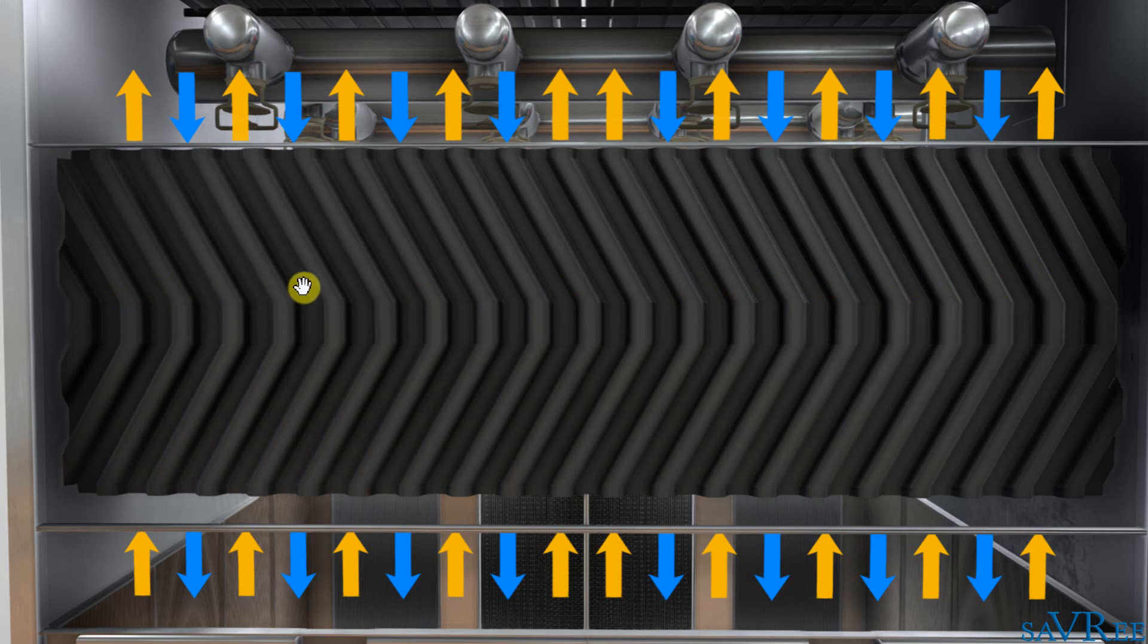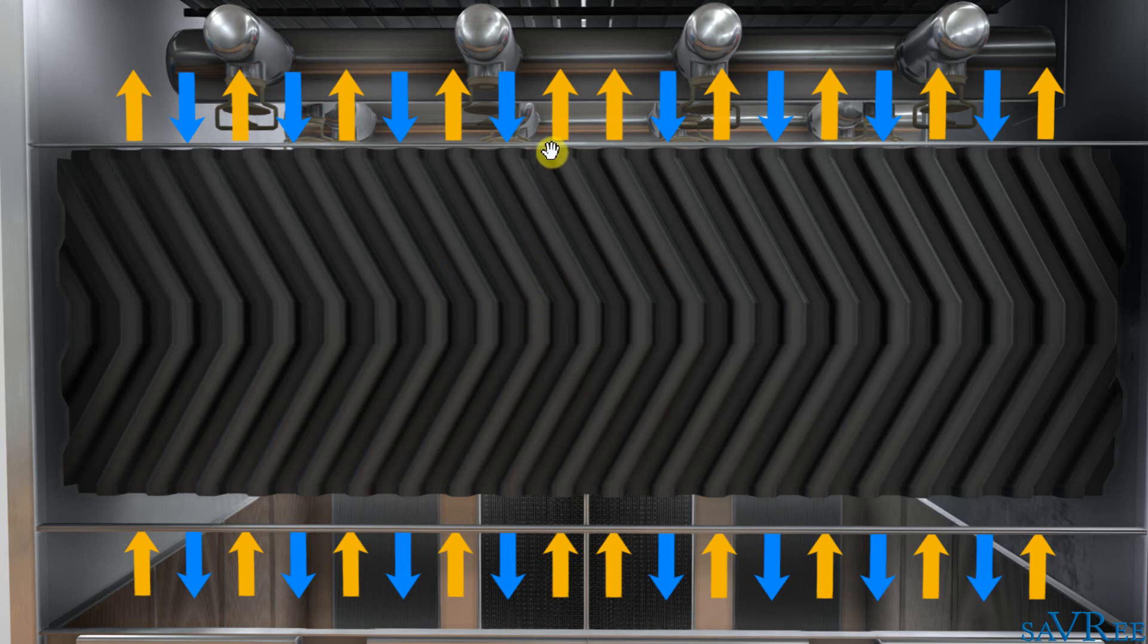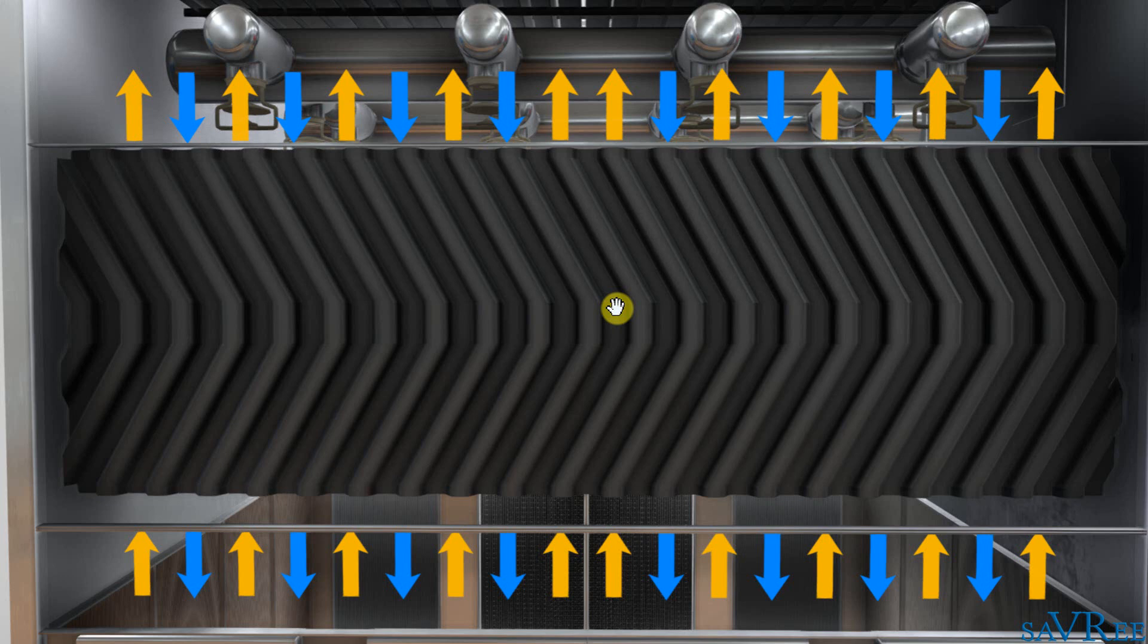So we've got this huge cross sectional area. We've got the water spread very thin across the entire heat exchanger or the entire fill. And that means that as the air passes over this very thin film water, we're going to get some of that water evaporating. And as it evaporates, it's actually going to cool the water molecules that are surrounding it. Now if you want to learn more about this, then you need to go and look up the latent and sensible heat lesson that we covered earlier in the course.